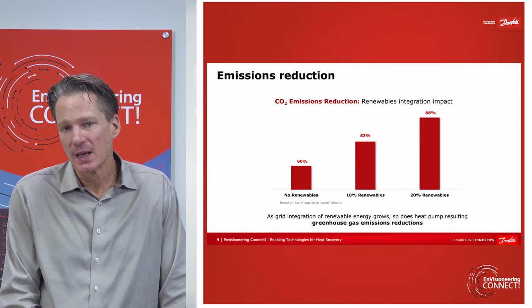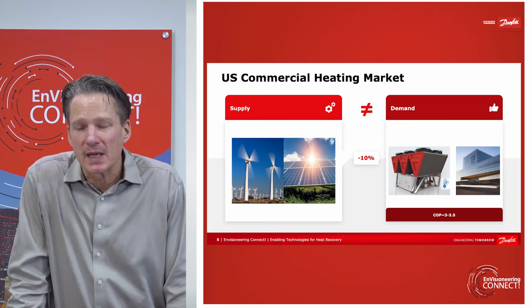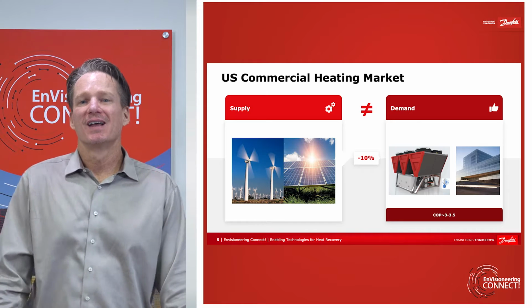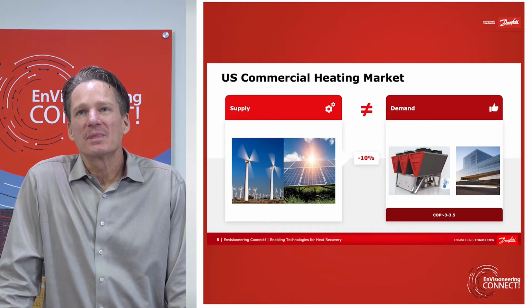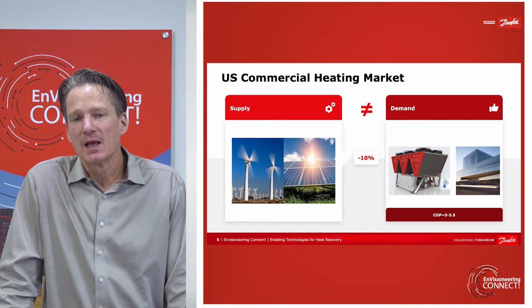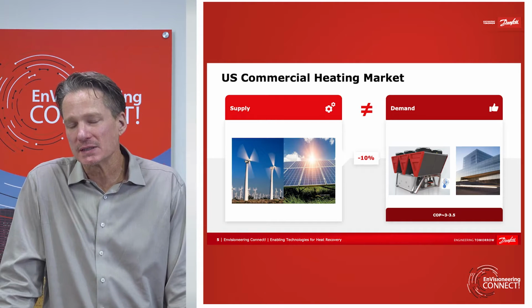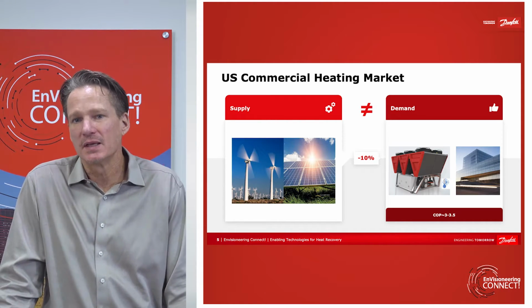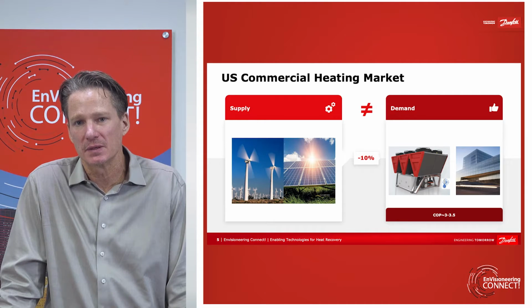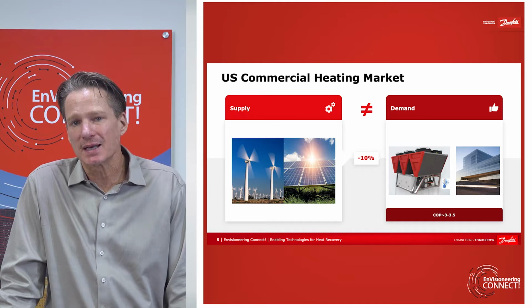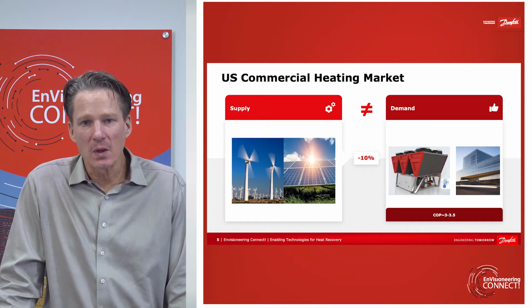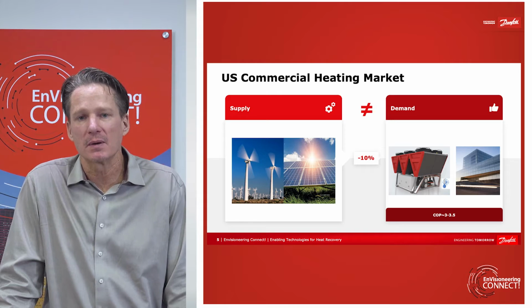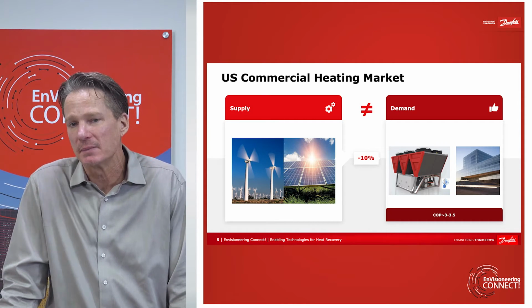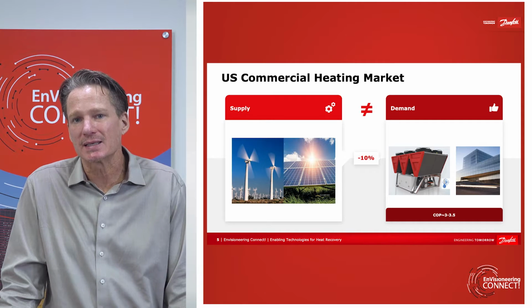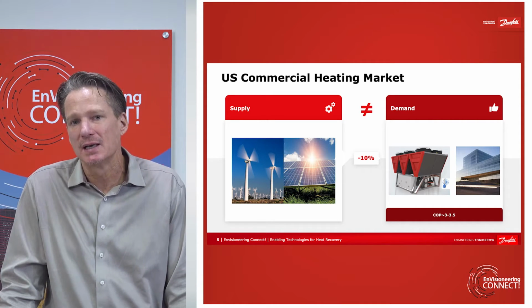But the problem that comes into play, as you integrate more renewables into the power grid, is that the integration of those renewables creates a disconnect between supply and demand. As a higher percentage of your power is coming from the sun or from wind, you're at the mercy of the availability of those resources. So no longer do you have supply that's governed by demand; you have supply that's governed by the availability of those resources. That disconnect has to be addressed, and how you address it is with storage.